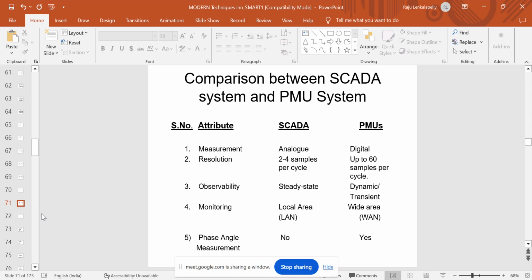In terms of monitoring, SCADA covers a local, small area, whereas PMU can measure over a wide area. Another important feature is that SCADA cannot measure angle - it measures voltage magnitude, but not angle. It will measure current, but for current angle we need a separate system. In case of PMU, it measures both voltage and its angle, as well as current and its angle. This fifth point is very important with respect to SCADA versus PMU systems.